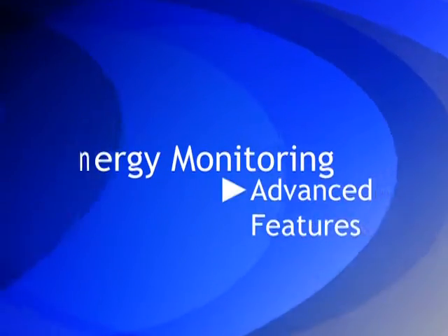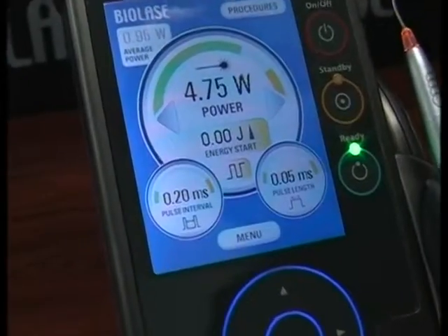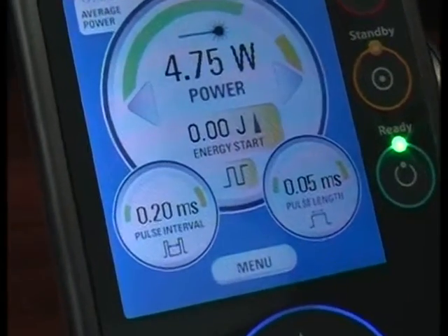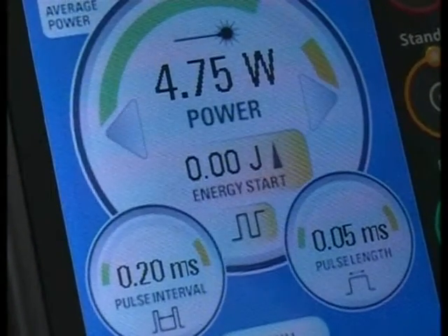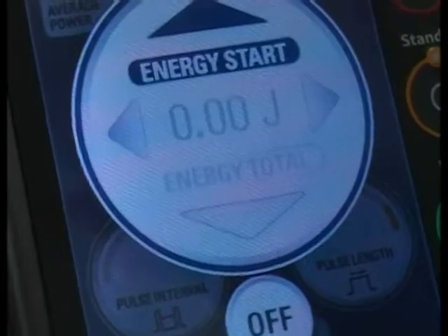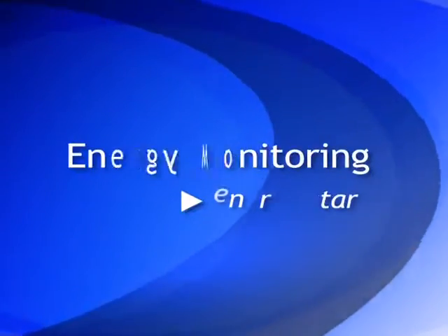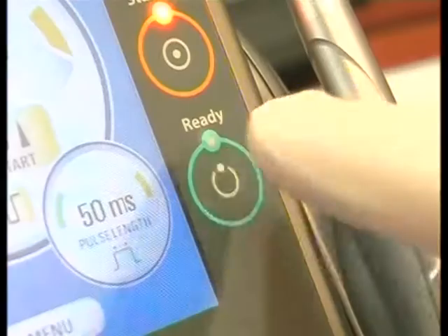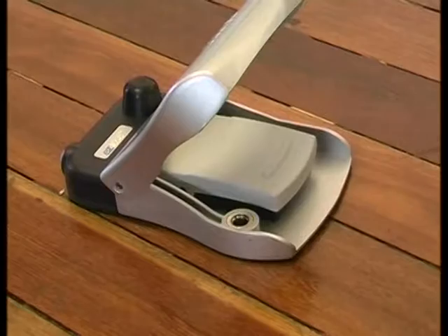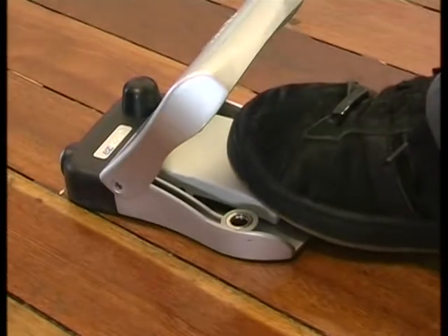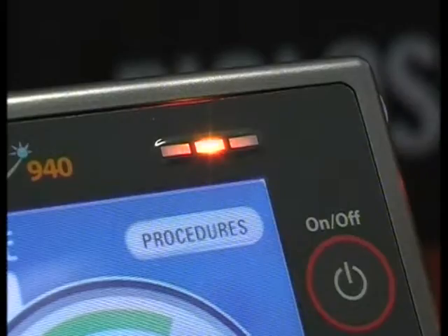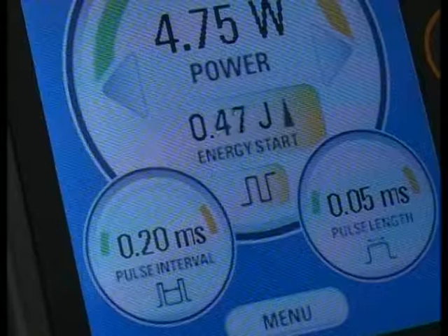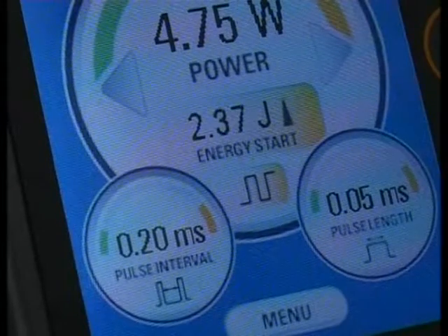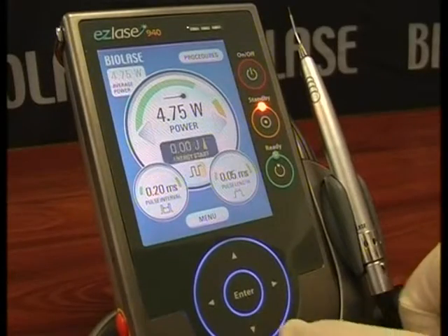Energy monitoring. The Ezlase has a unique function of energy monitoring. This can be seen on the touchscreen just below the power display. The energy monitoring program has two functions and can also be turned off. On the Ezlase, the energy start performs the same kind of calculation. When you fire the laser, the energy start feature will measure the total amount of energy delivered during the procedure. It is measured in joules, the standard unit of measure of energy. This function can also be selected using the click wheel.